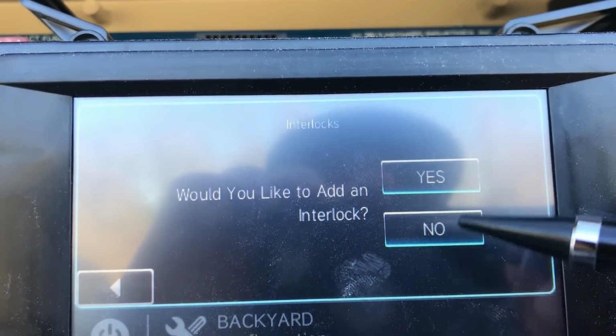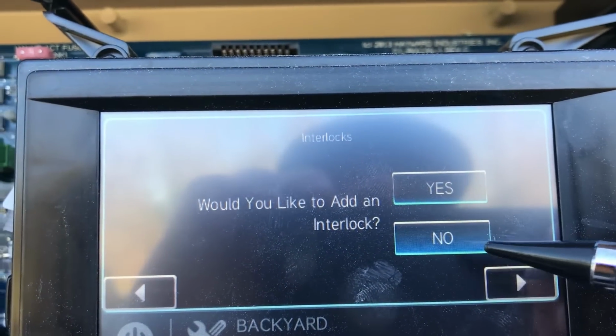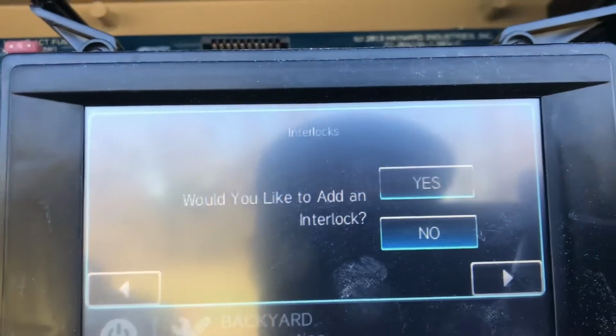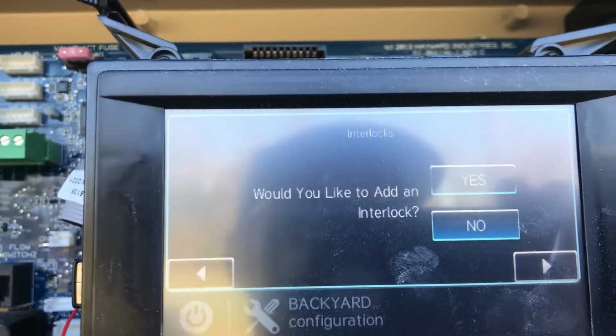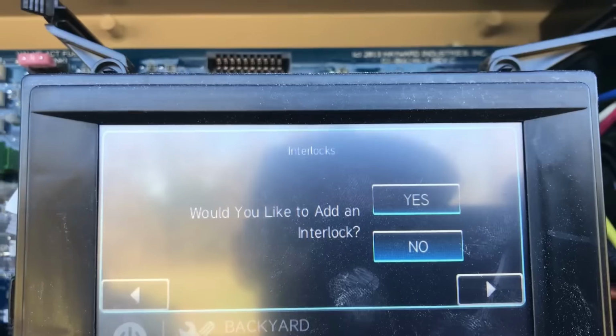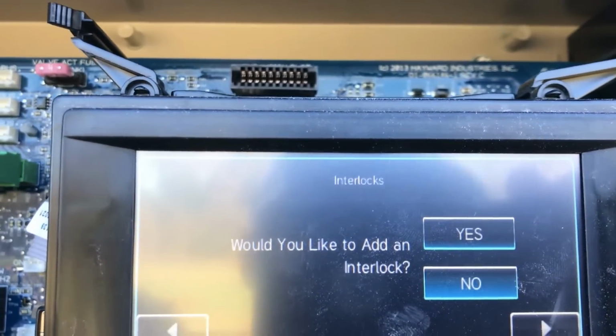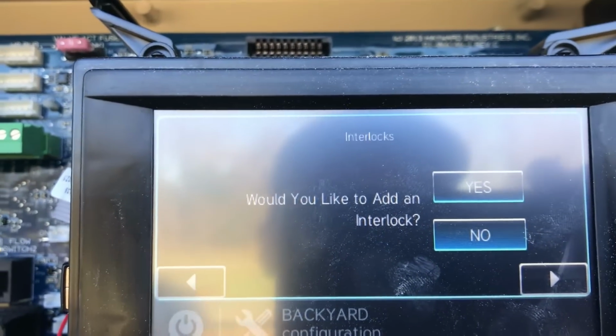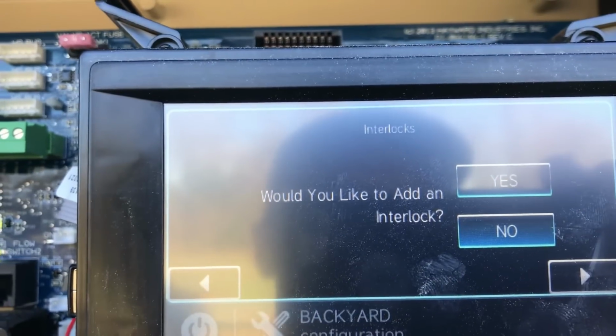We'd like to add any interlock? I say no to adding interlocks. An interlock, for example, the main one you would add is setting up the cleaner pump to not be able to come on unless the main pump is on.